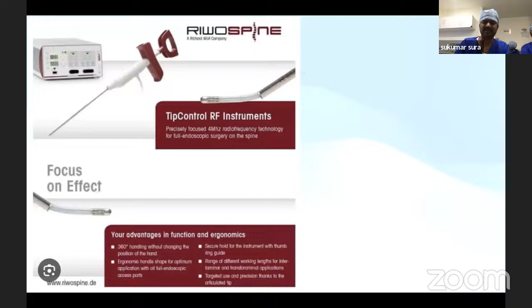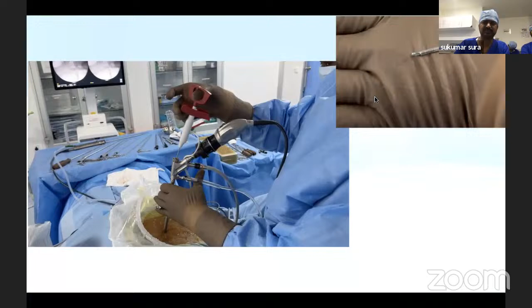Here I'm using coagulation. How do I teach this? To go to 12 o'clock, I just have to press it. It opens up at 12. If I want to go to 6, I just rotate it, and it goes to 6 o'clock. For 3 o'clock, I just rotate, and for 9 o'clock, I rotate to the top position. So you need not rotate your wrist. You can see here, I'm just rotating the handle. So I can go all around 360 degrees without touching the probe when I push.